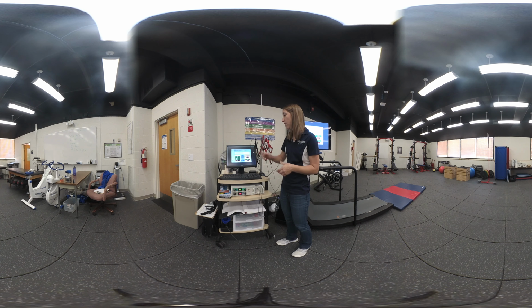So the first thing it does is it tells you to flip this switch on the front of the metabolic cart on. An important factor here is I had the metabolic cart plugged in and turned on for 30 minutes before I came in to do this test. So you always have to give the machine at least 30 minutes of warm-up time before you run any sort of calibration or any sort of test with it.